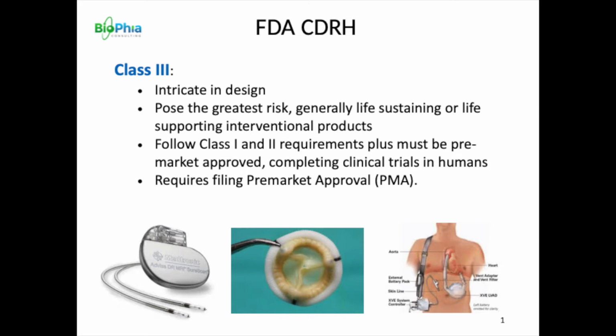There's more examples that you can see on the website. The approval process is called a pre-market approval, a PMA, and it requires that you do a clinical trial, through the investigational device exemption, the IDE, which is part of this process, and that all is to demonstrate the safety and the efficacy of this new device. So that's a class 3 approval.